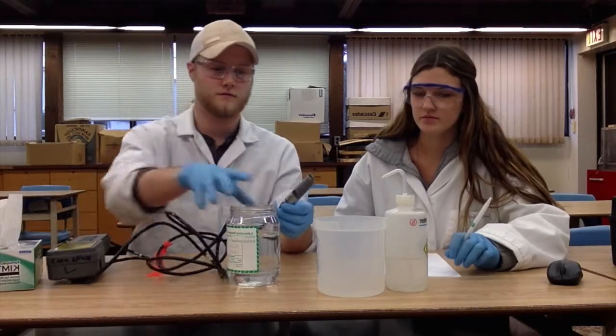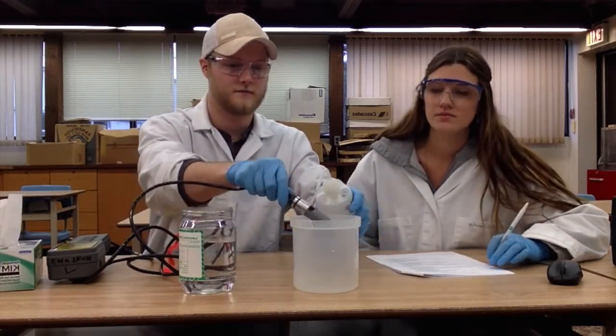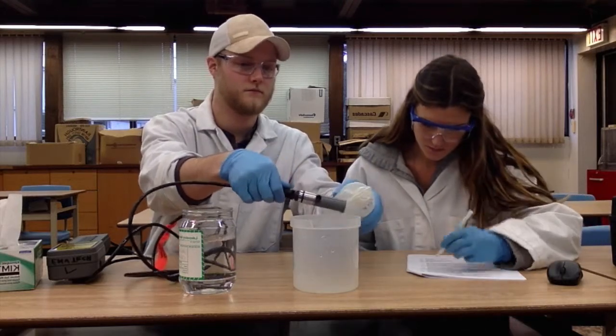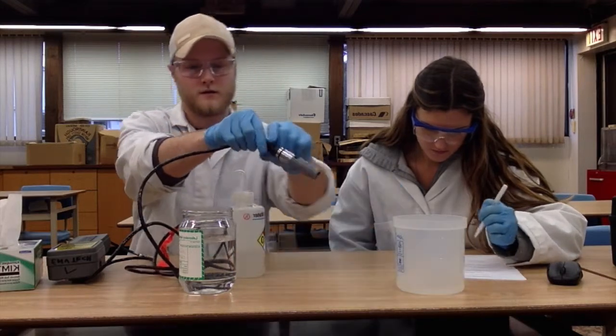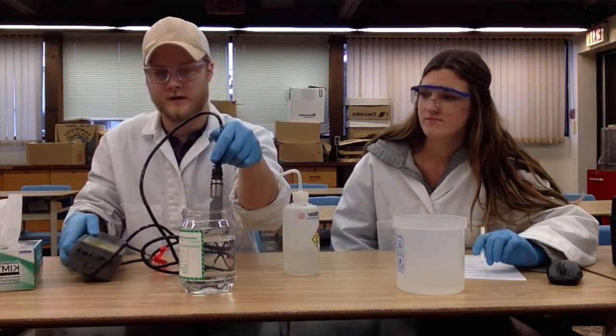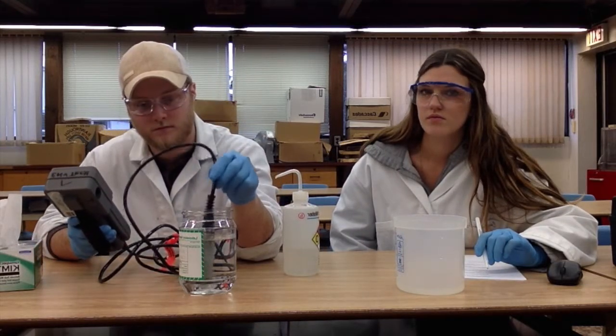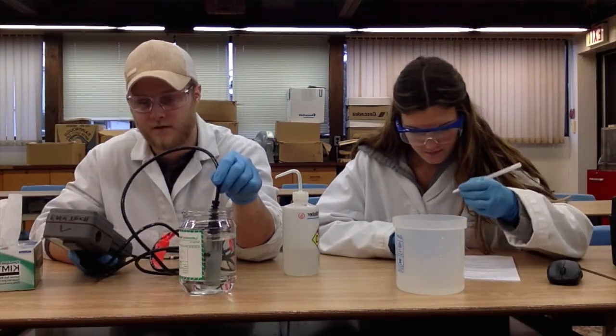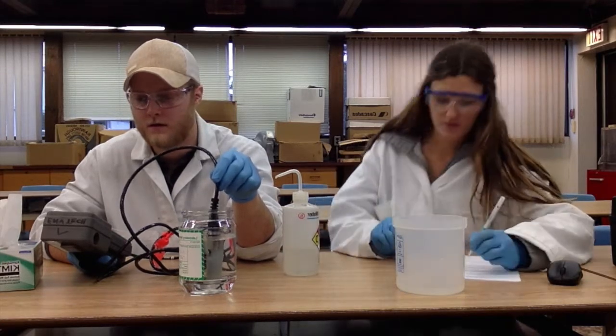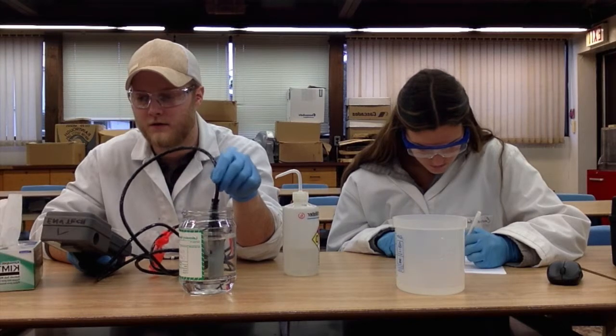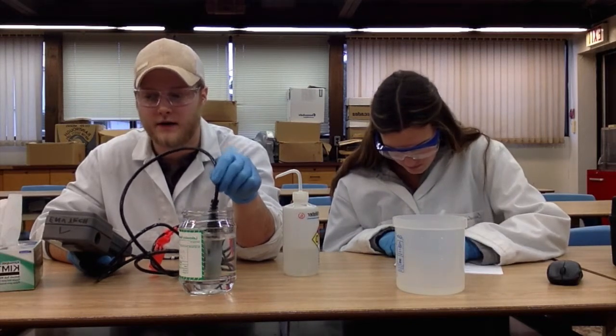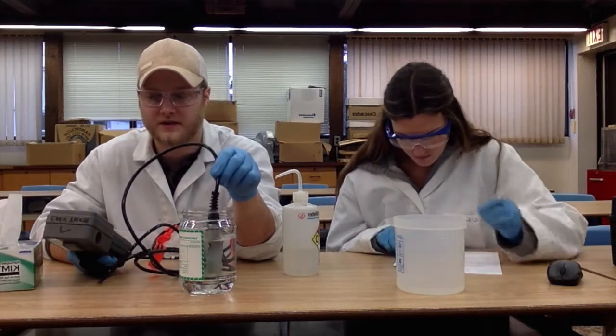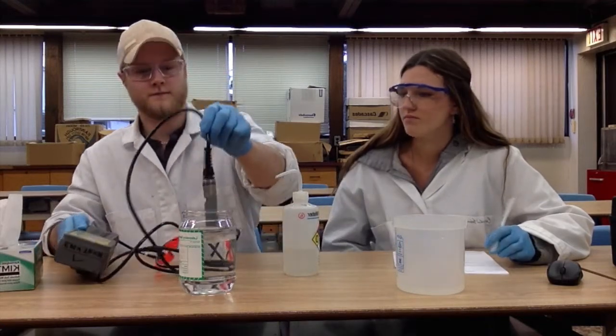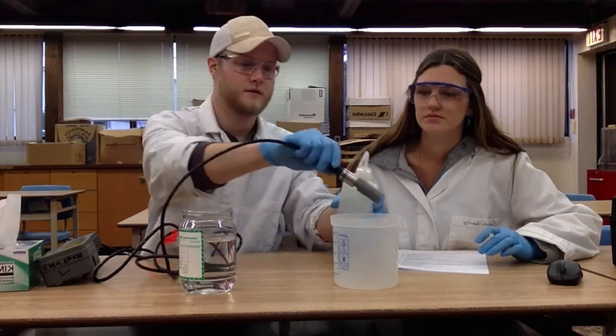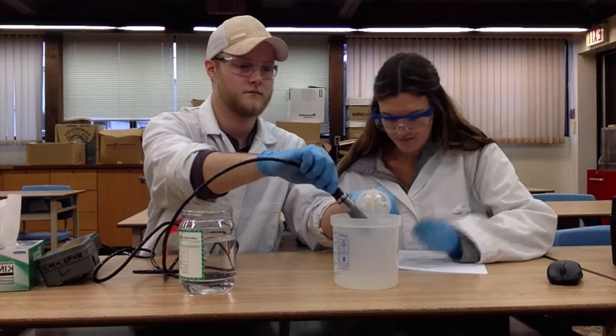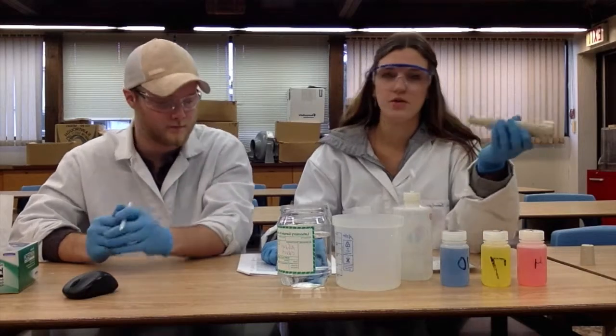So we want the proper conductivity for what the temperature is going to be. So we're going to take the probe, rinse it with distilled. Take it and put it in our sample bottle. Make sure to bob the probe. So the reading I'm getting is 503 microsiemens at 20.3 degrees Celsius. Take this probe out of the sample and rinse it with distilled. And that's all.